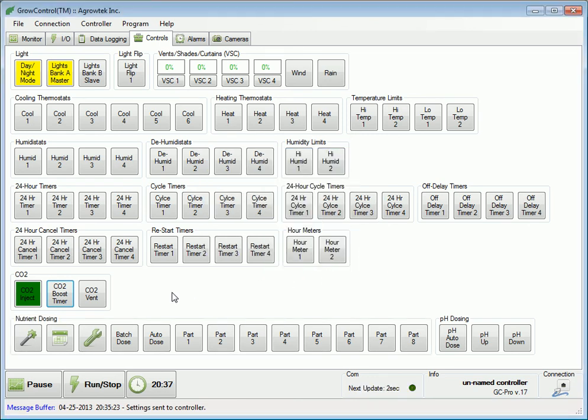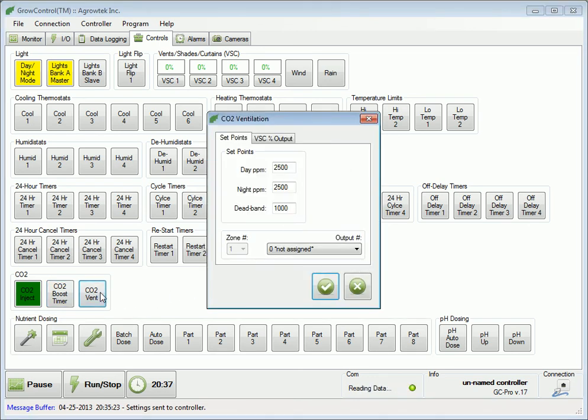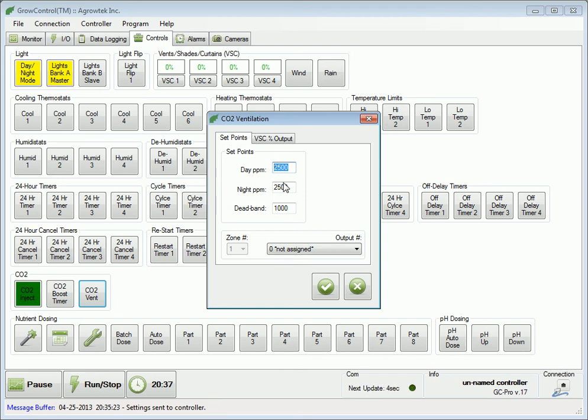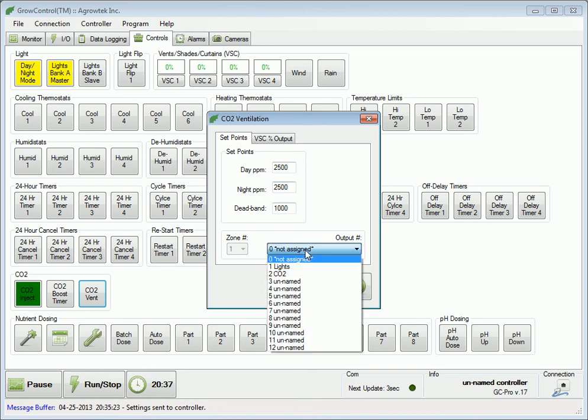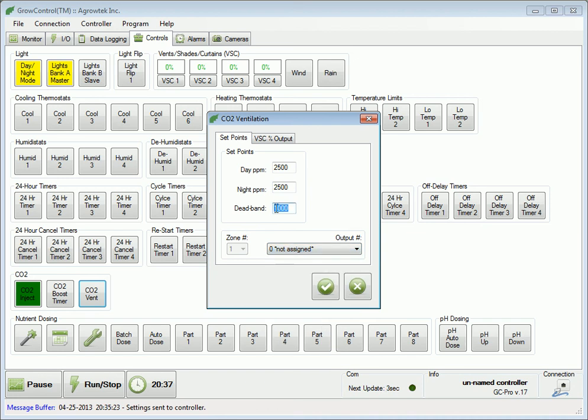CO2 vent controls allow the system to operate an output if the CO2 level rises above a certain set point. In this case, if the CO2 level rises above 2,500 PPM during the day or night, a selected output will be operated. The output will remain operating until the CO2 level drops by 1,000 PPM to below 1,500.